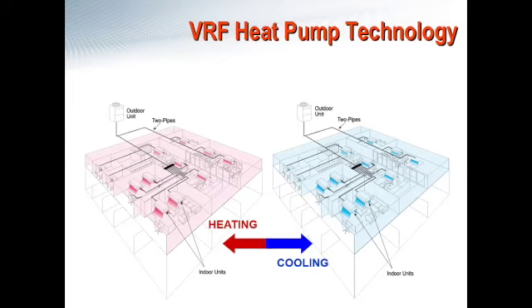So this system is going to act where all of your indoor units are going to be providing heating, or all of them are going to be providing cooling. One important caveat to this is that each individual zone can provide a different level of heating or cooling. So say you have one room that only requires a little bit of heat or a little bit of cooling, while another zone that may have a lot more occupancy or solar load is going to require more heating or cooling. That can be accommodated. But while that is the case, all of the units are going to need to be acting in the same mode at any given time.